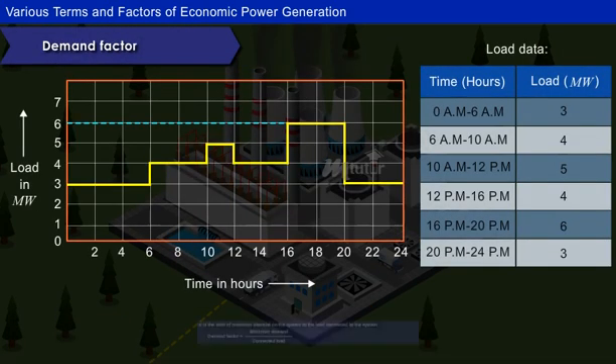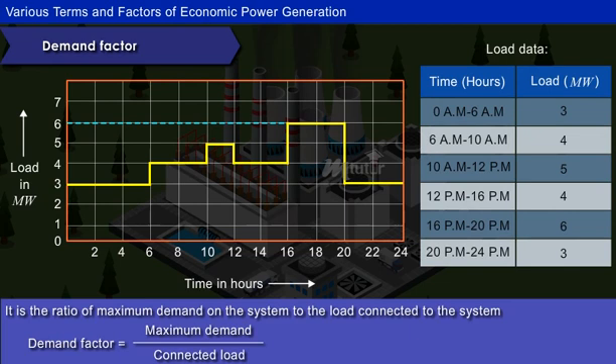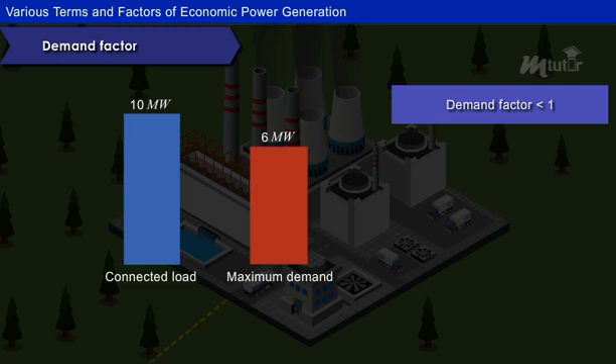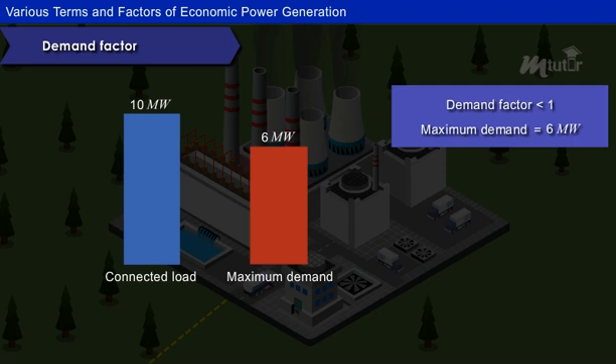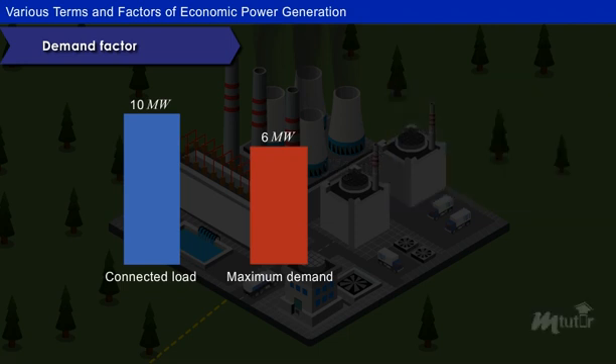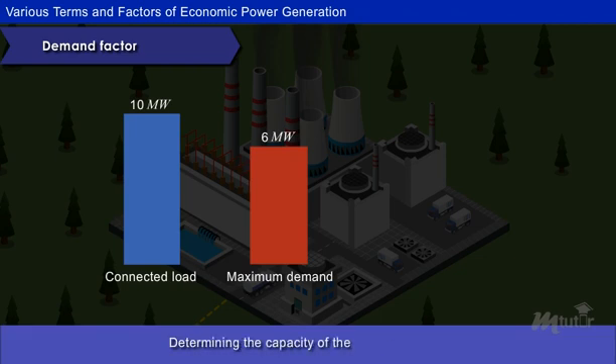Demand Factor: It is the ratio of maximum demand on the system to the load connected to the system. It is always less than unity because maximum demand on the power station is generally less than the connected load. For example, the maximum demand on the power station is 6MW and the connected load on the power station is 10MW. Then, the demand factor is equal to 6 divided by 10, which is equal to 0.6. The demand factor plays a vital role in determining the capacity of the plant equipment.